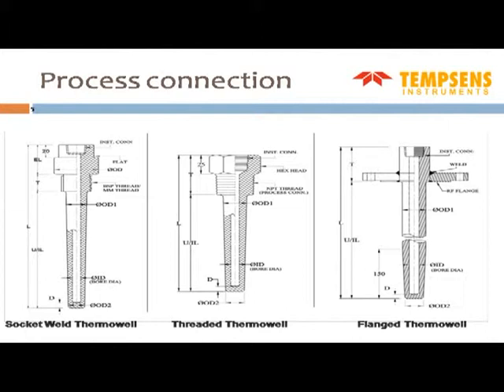This is a socket weld construction, the first one on the left side, then the threaded connection, and then the flange connection, the same thing shown graphically in diagrams. You see various kinds of nomenclature here. EL represents the extension length, which is outside the process. T is the threaded connection. L is the overall length, and IL is the insertion length. This is the standard nomenclature for the thermowell. Various kinds of flanges, process connections and threads are available as per the requirement of the customer.